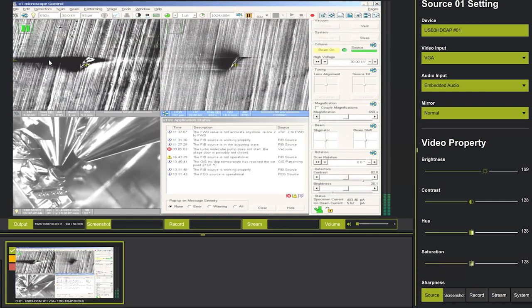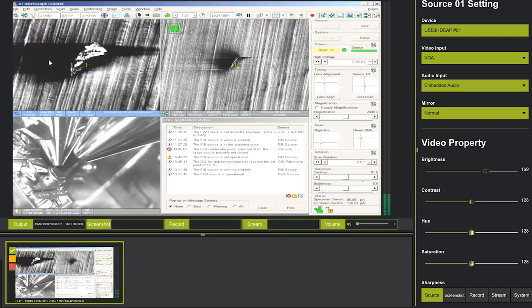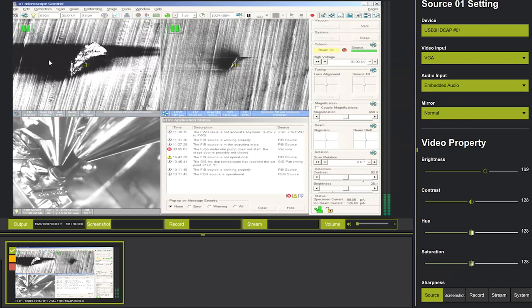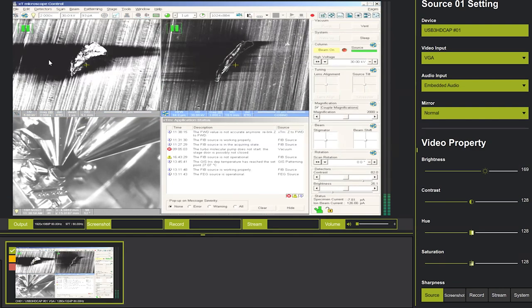Let me pause here. I didn't move the stage; I just switched the imaging mode to the ion beam mode. Now both beams are hitting about the same location. The electron beam image is from an angle, and this is the ion beam image. So from top down, this particle sitting on the surface looks like this, but with the electron beam it looks different because the view isn't from the same angle. It's important to find the Z height by hitting two spots.